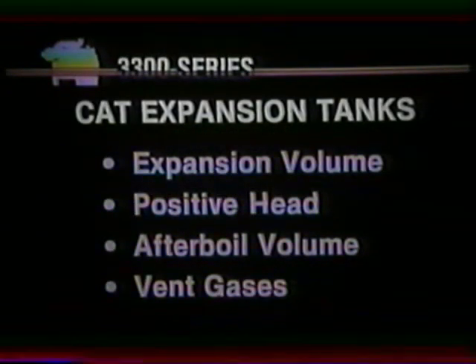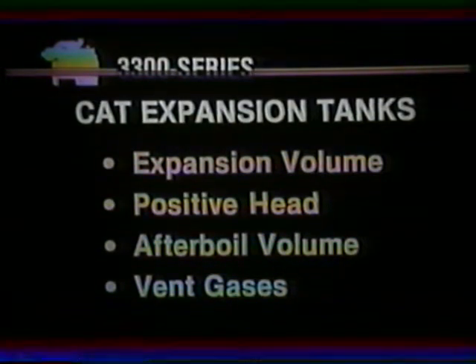All keel-cooled and heat exchanger-cooled engines must include Caterpillar expansion tanks. In addition, keel-cooled engines generally require a customer-supplied auxiliary expansion tank. The engine-mounted Caterpillar expansion tanks do more than provide expansion volume for coolant. They also provide a positive pressure on jacket pump inlets to prevent pump cavitation, provide afterboil volume, and vent entrained gases from the jacket coolant.